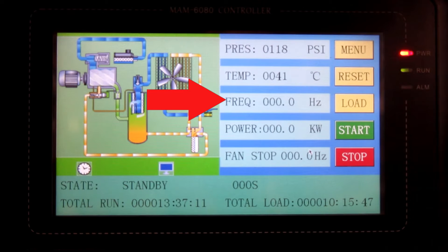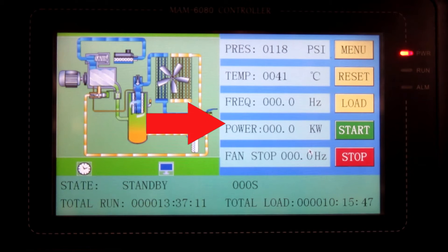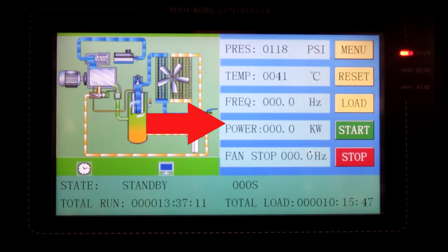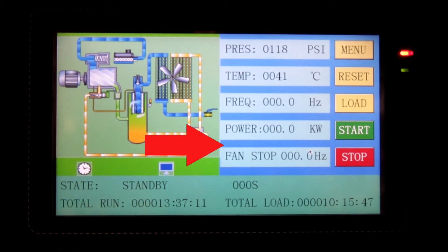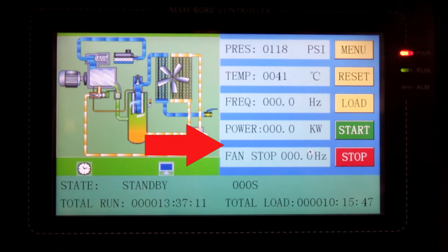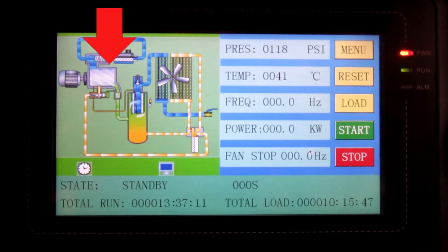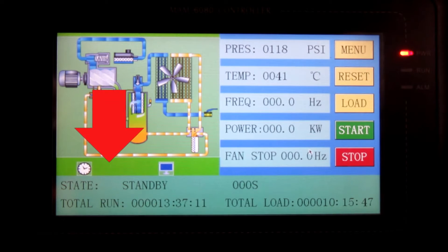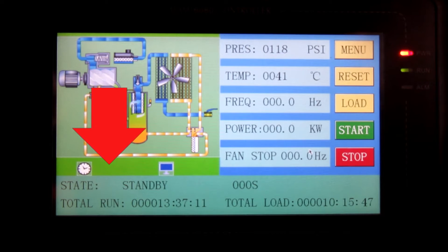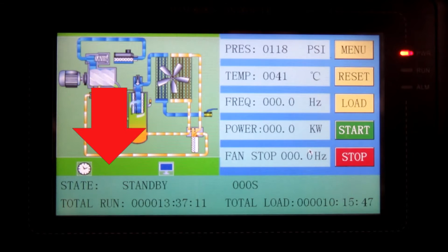The power reading is the draw, the kilowatt draw of the motor at its current time. The bottom reading is the fan, which is the cooling fan Hertz reading and its status. The bottom line indicates its run hours of the machine and the load hours of the machine, and also the status of the operating condition of the compressor at its current moment.